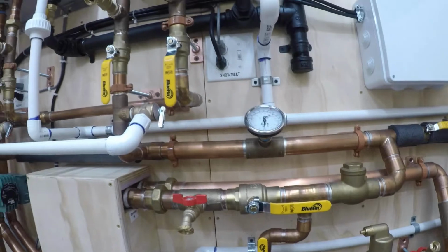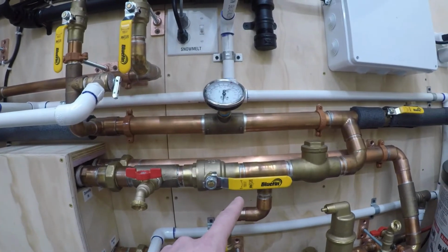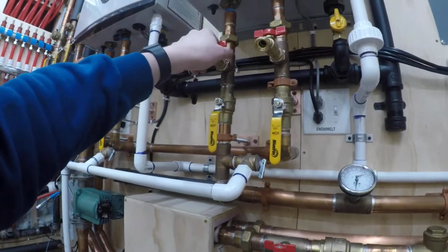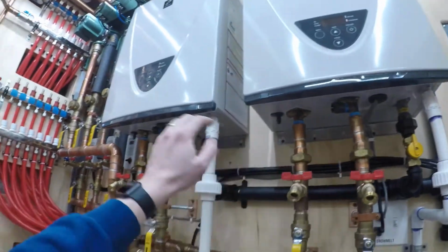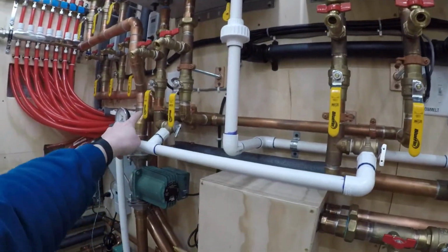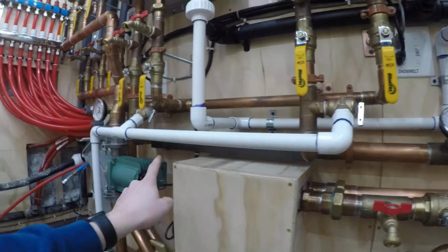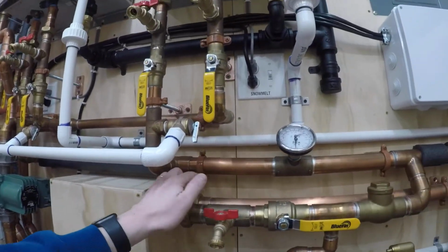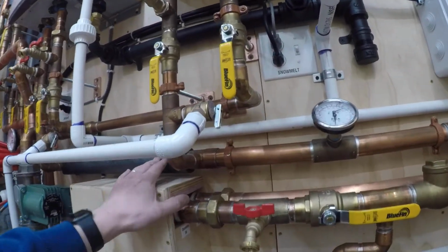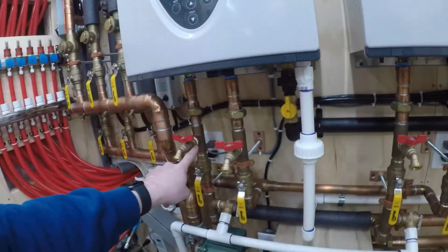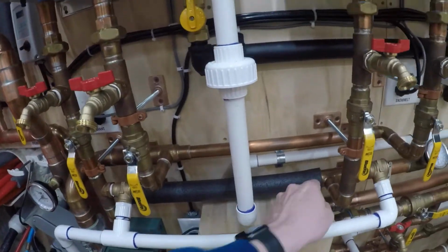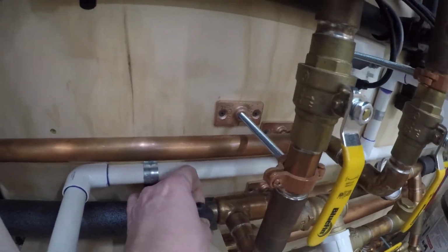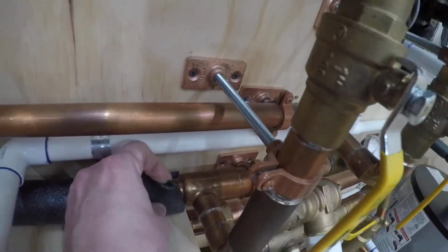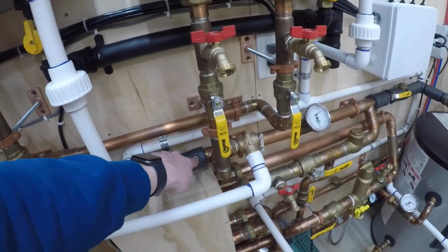Now once you get up here, coming from the heaters, you've got your hot out, reverse return like that, like I talked about. Here's your hot, comes back there. I've got to finish insulating it. This is all 1.5 inches. This is 1 inch, this is 1 inch, the 1 inch goes down, this is all 1 inch back here, and then back here it goes to like a 1.5 by 1.5 by 1 inch T.